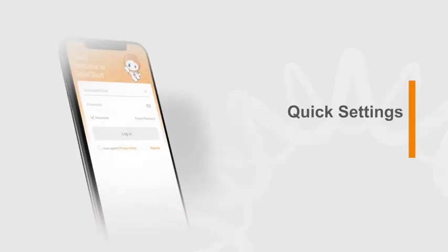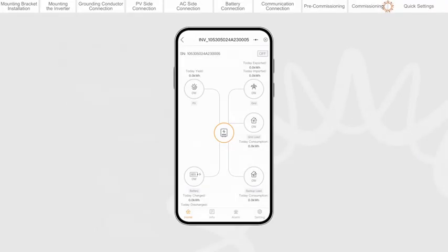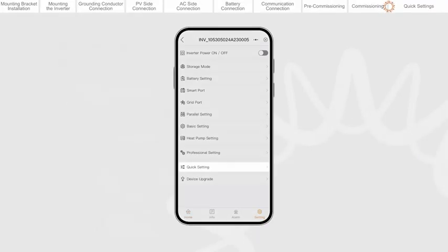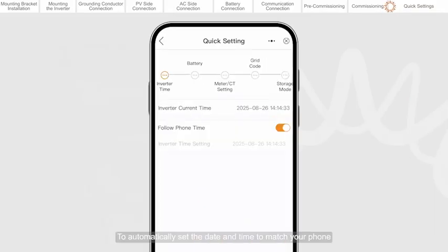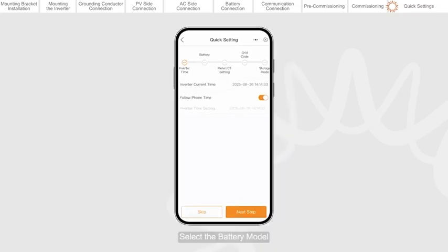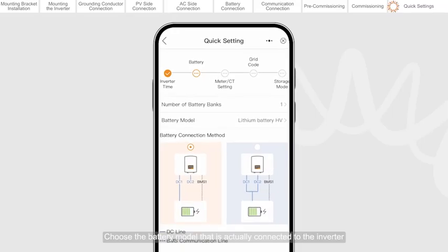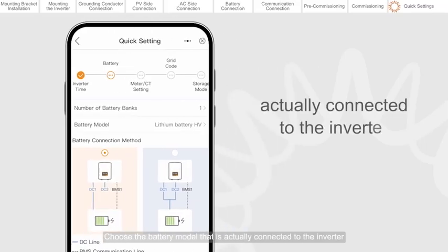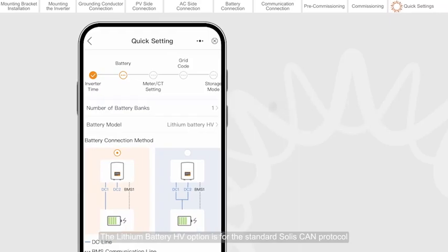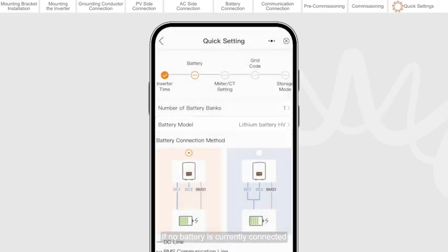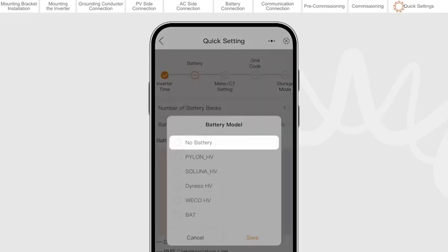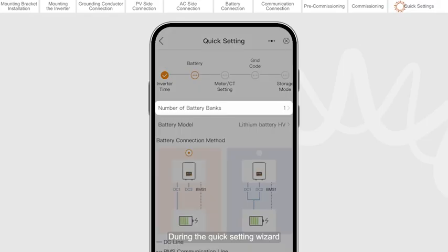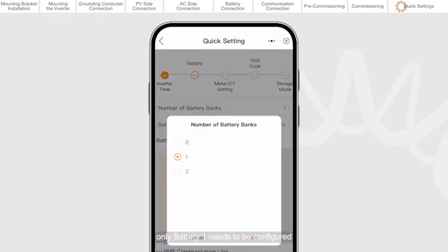Quick settings. Set the date and time. To automatically set the date and time to match your phone, toggle on the Follow Phone Time switch. Select the battery model. Choose the battery model that is actually connected to the inverter. The lithium battery HV option is for the standard Solis CAN protocol. If no battery is currently connected, select No Battery to avoid alarms. During the quick setting wizard, only battery 1 needs to be configured. Battery 2 can be set later.